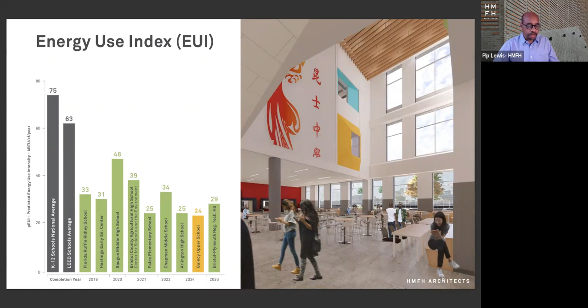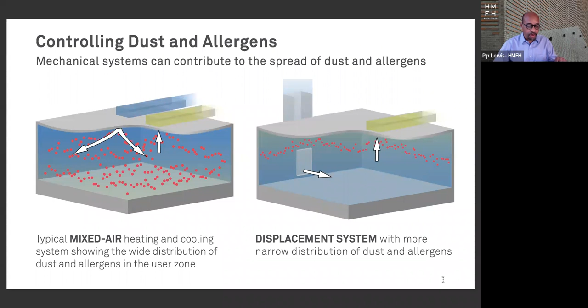Next. Now to explain displacement ventilation and contrast it with the traditional mixed air method that we're all used to seeing. In mixed air systems, warm or chilled air, depending on the season, is projected into the room at a relatively high speed to mix with other air to reach the desired temperature. In displacement, however, large quantities of air are allowed to flow out low across the room at a slow speed, displacing the existing warm air there. The occupants themselves in the room heat the air slowly, and it will rise vertically to the ceiling where it's exhausted. This vertical motion limits the spread of dust and allergens around the room, in addition to providing a very good and very quiet indoor air quality environment.